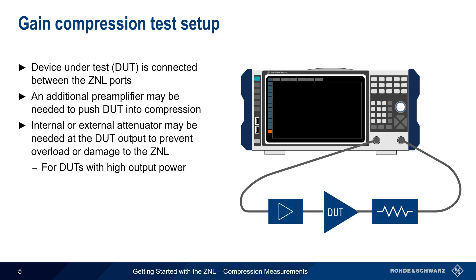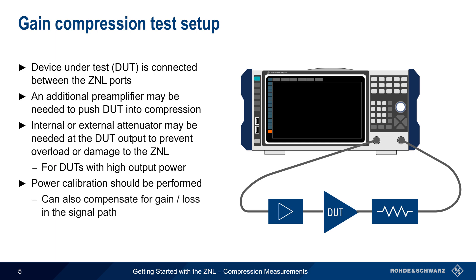As mentioned a few moments ago, a power calibration should be performed before making gain compression measurements. In addition to improving measurement results, this calibration can compensate for gain or loss in the signal path, such as that caused by preamplifiers, attenuators, etc.